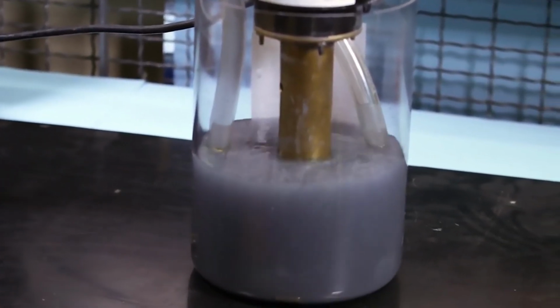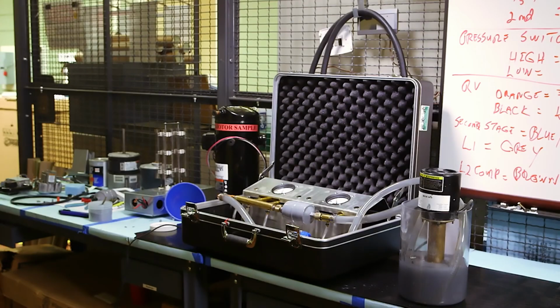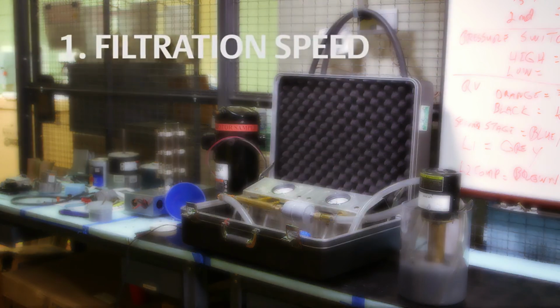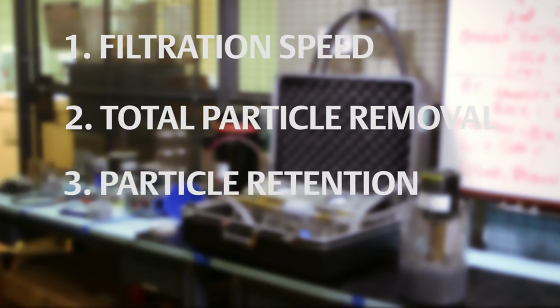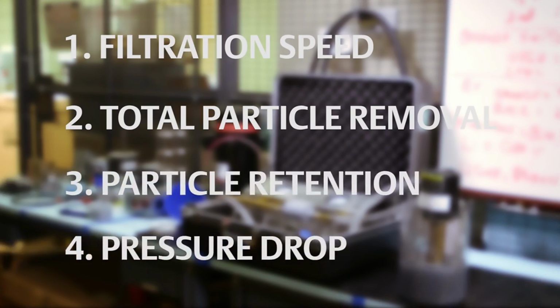There are a few factors to consider when it comes to filter dryer filtration. First, the speed at which the filter dryer removes the particles from the system. The faster, the better. Second, total particle removal capacity. More is obviously better. Third, the ability to retain those particles. And lastly, the pressure drop across the dryer versus the amount of grit capture. Significant pressure drop is detrimental to system capacity.